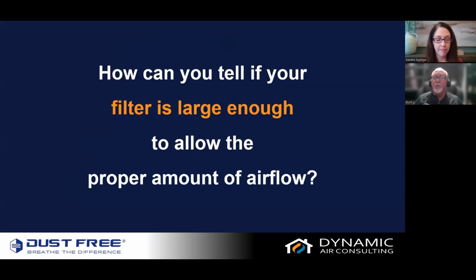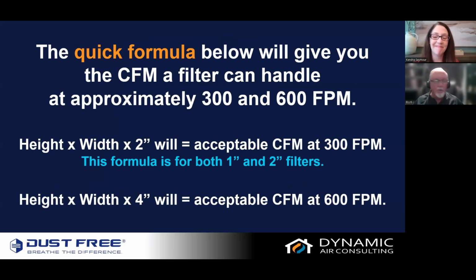So how can you tell if your filter is large enough to allow the proper amount of airflow? This is from the National Comfort Institute. Their whole world is airflow and static resistance, but here's a quick formula to tell if your filter can handle the CFM at 300 or 600 feet per minute. Height times width times 2 will give you the acceptable CFM for both a 1 or 2-inch filter. And height times width times 4 will give you the acceptable CFM at 600 feet per minute. So if you go up to a filter, pull it out, and do this calculation real quick, you can say, hey, based on this calculation, it can't handle it, or it can. Or do I need more than one filter in place? So this is for the HVAC people in the group.